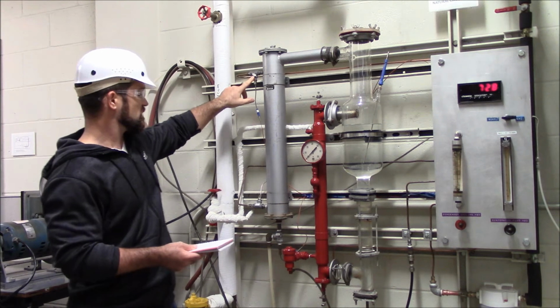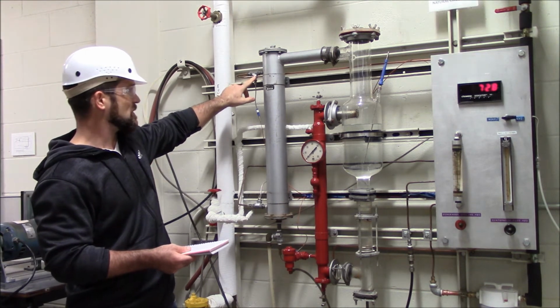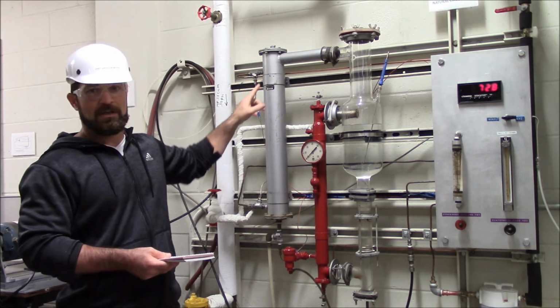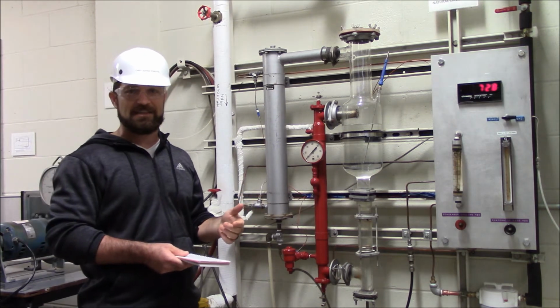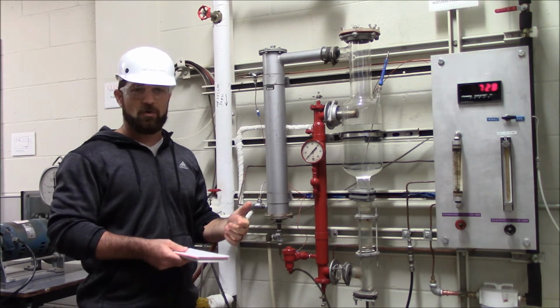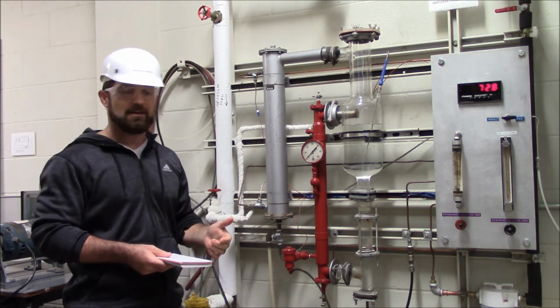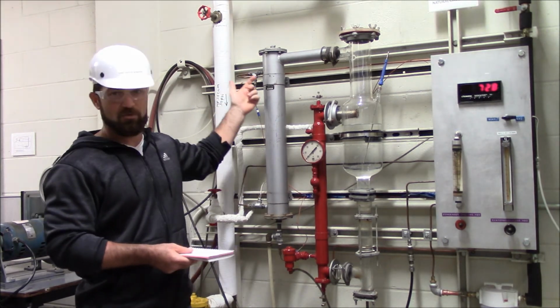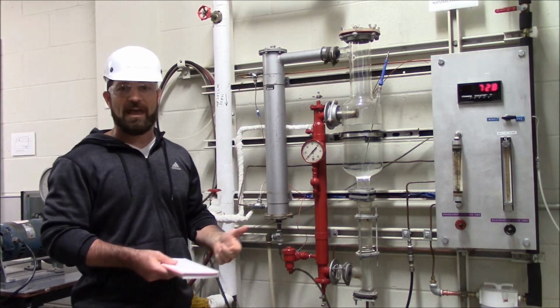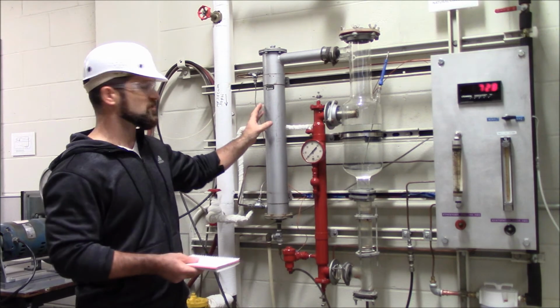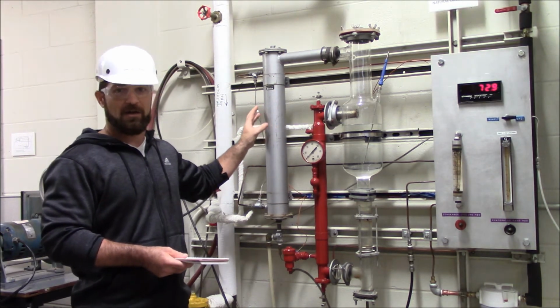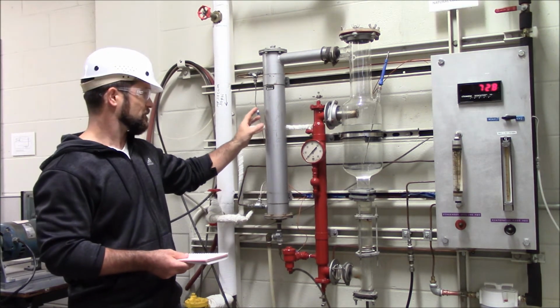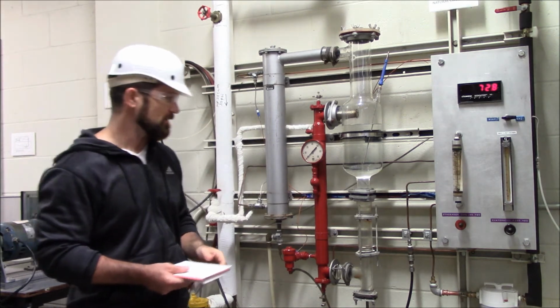A measurement of the cooling water temperature coming out is going to be TC2. It's important for this measurement that you have at least a 10 degree difference, or as close to a 10 degree difference as possible, in the temperature entering and exiting the cooling water, to give you the most accurate determination of how much heat is being pulled out of this condenser for the overhead condensate.